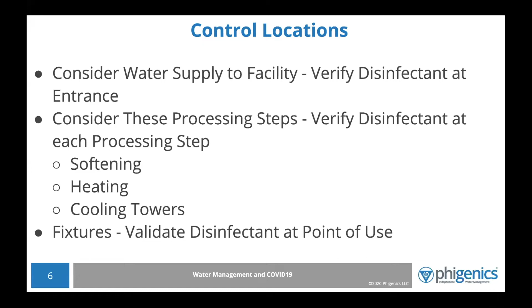At the entrance, you may need to flush water. And when we say flush water, I would start in the range of 1 gallon per minute, which is 1,440 gallons per day. It certainly depends on the facilities around you, how big your supply line is, but that's the kind of magnitude when we say flushing you need to look at. Again, once you begin a flushing protocol, you want to verify that the flushing accomplished what it did. So where can you flush? You certainly can flush at the entrance. If you have a very low census or low occupancy, and you're not adding supplemental disinfection, flushing the heating hot water recirculating loop, starting with 1 gallon per minute is a very good idea. It's a small amount of water. If you're spending $10 per thousand for sewer or for purchase and sewage, that's $10 a day, not a lot, to make sure that you don't foul that heating hot water system.